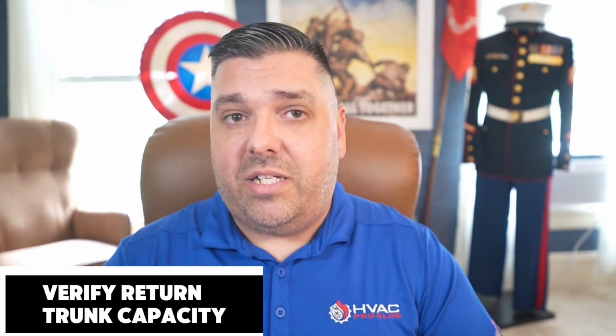Step 2, you need to verify return trunk capacity. Now here's where the old wives' tale needs to die. Yes, return air matters, but it's not just about making ducts bigger. Pull out your duct calculator and check 2 things. Can the return trunk handle the full volume of air? And what's the velocity? Return trunks should run between 500 to 700 feet per minute. Any higher, and you need a larger return or an additional path from this return plenum.